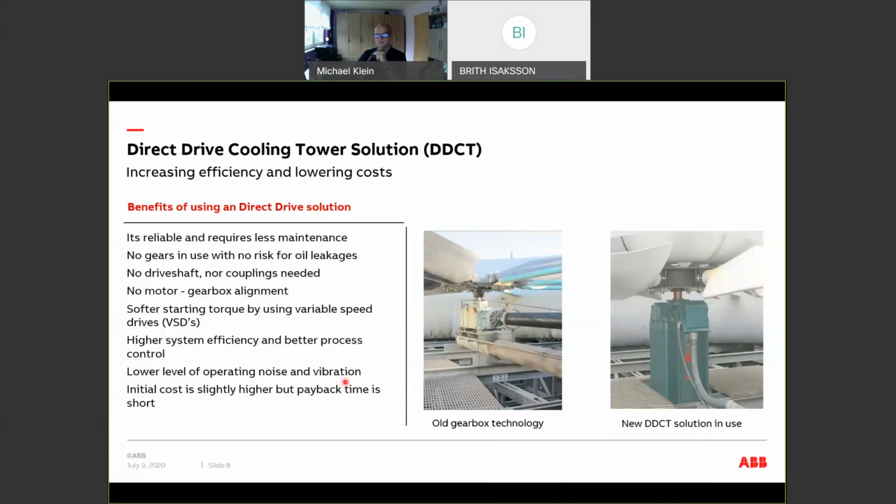Yeah, we are having less material, like I said, and we have less vibration on this entire system. One thing maybe that can be explained here is the fan and the shaft are quite near to each other. So if the fan turns, think about it, there is a freewheeling on 3/4 of the tower, let's say, or even more. And then when the shaft comes here, it's a kind of an air cushion that is generated between the fan and the shaft. So that means that the fan is pushed up actually. It's slightly pushed up when the fan comes over this drive shaft. And that causes vibration, of course.